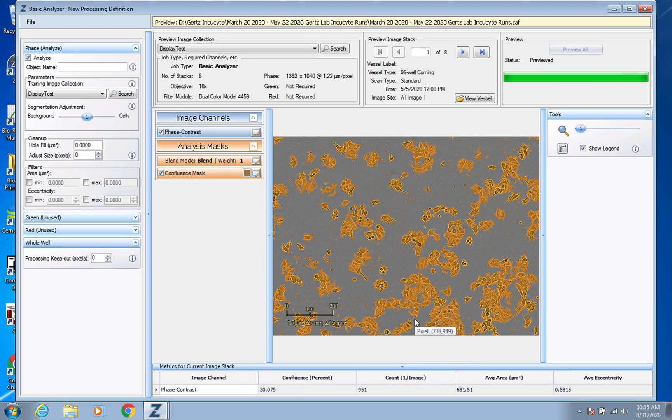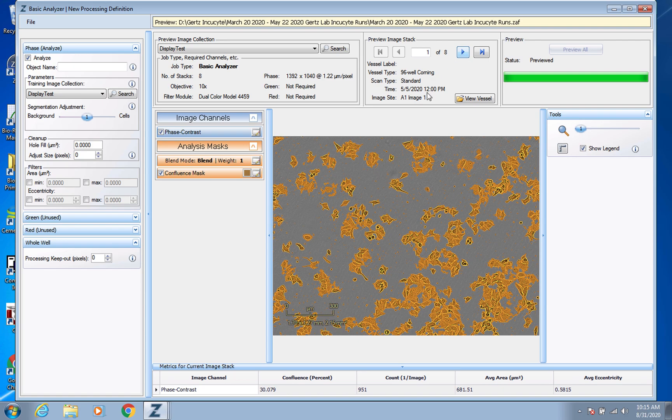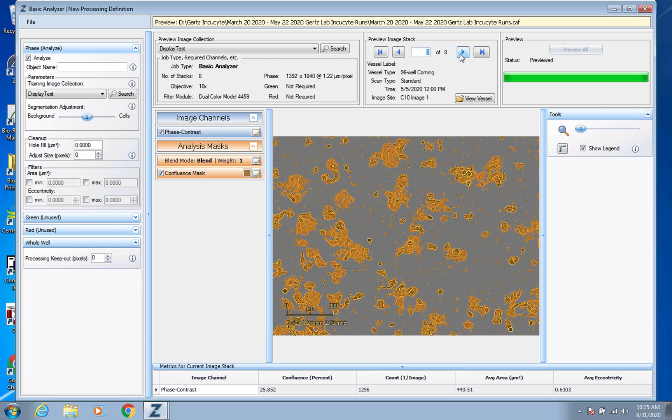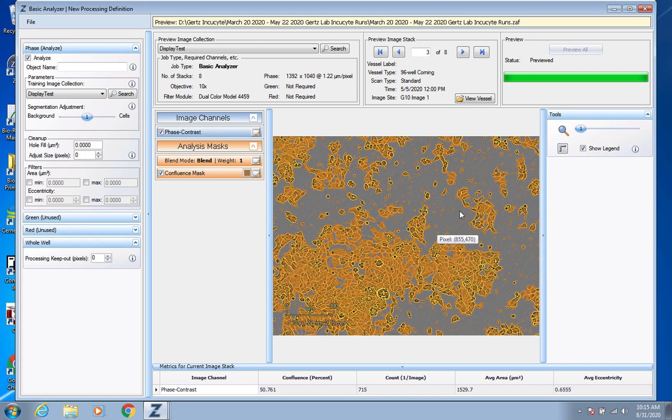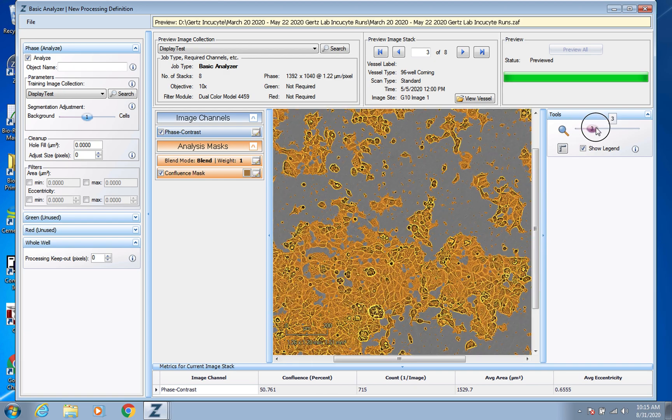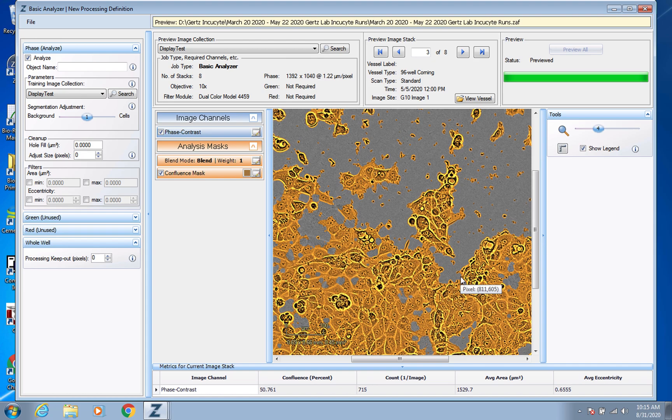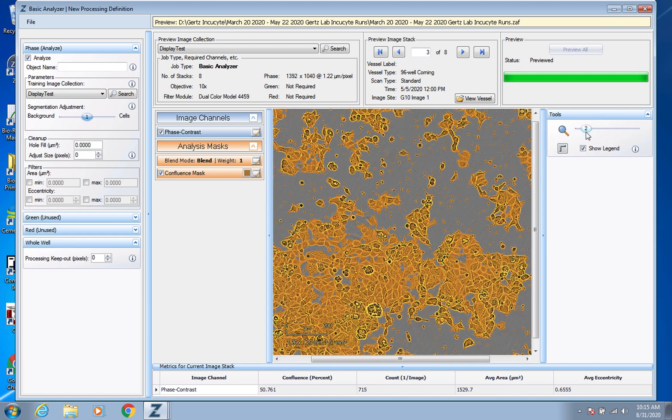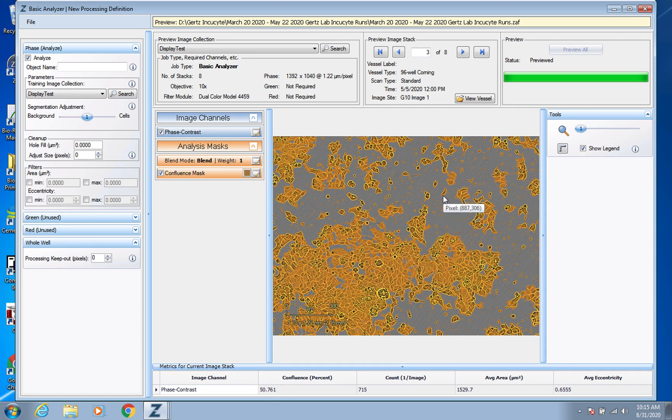So how it's deciding that data. So right now, it's looking at this and telling you that it's about 30% confluent and showing you exactly what it believes is cells. And you can see it is picking up a lot of this debris. If it was more, that might be more of an issue. You can definitely see it here too. So that might be something we can change up here. But other than picking up all that debris, if you zoom in using this tool over here in the top right, you can see that it is detecting the cells pretty well. And it's coming in real close to them. That's one of the things you can look for. So that part looks pretty good. And it's overall fairly accurate in the percent confluent it's giving you. You know, we're not looking at this and it telling us that this is only 10% confluent or something like that.